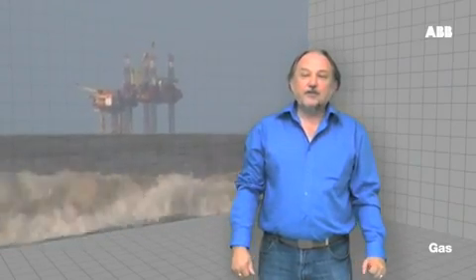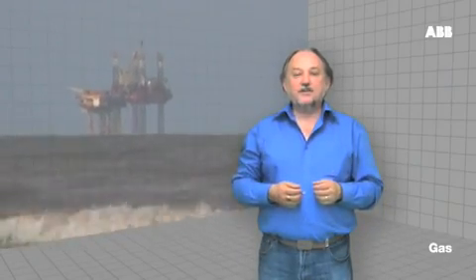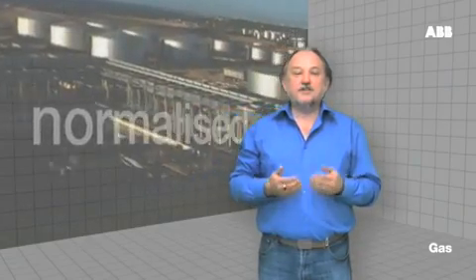Engineers frequently express mass flow measurements in volumetric units. However, to be able to compare volume-based flow rates, it is necessary to introduce standard or normalised conditions for temperature and pressure.